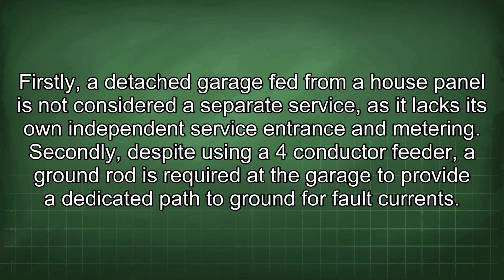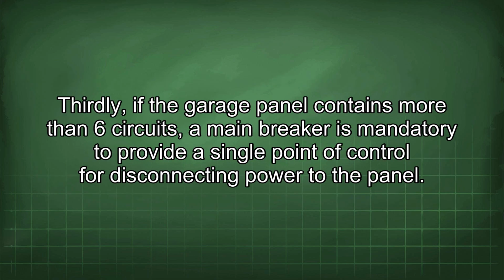Secondly, despite using a 4-conductor feeder, a ground rod is required at the garage to provide a dedicated path to ground for fault currents. Thirdly, if the garage panel contains more than 6 circuits, a main breaker is mandatory to provide a single point of control for disconnecting power to the panel.